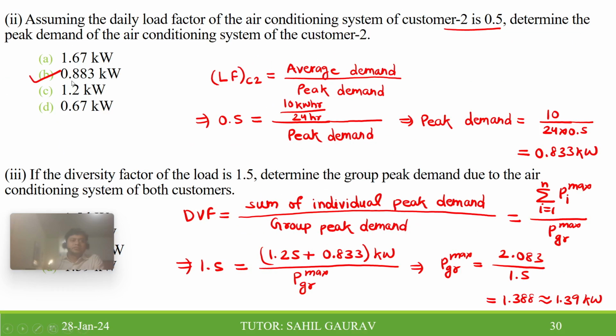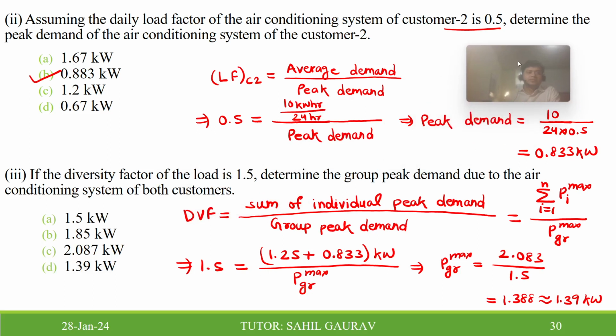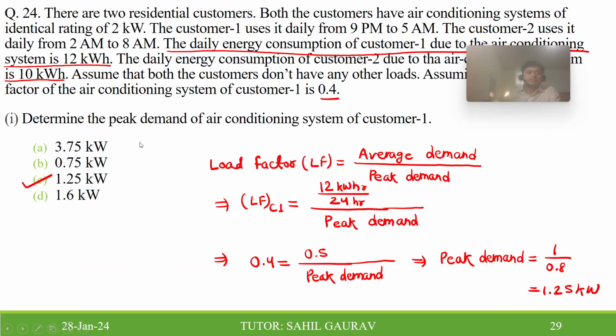Now the third part is: if the diversity factor of the load is 1.5, determine the group peak demand due to the air conditioning of both customers. So here, diversity factor, we know, is the sum of individual peak demand divided by the group peak demand. So diversity factor is 1.5. The sum of individual peak demand, we know, is 1.25 kilowatt and 0.83.